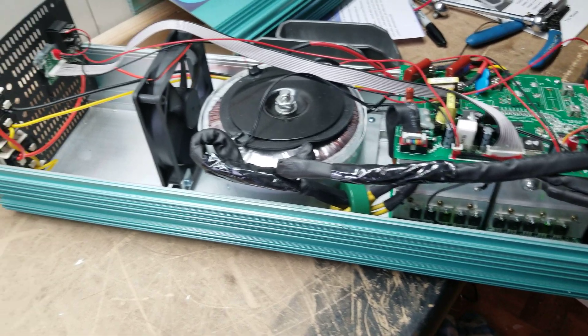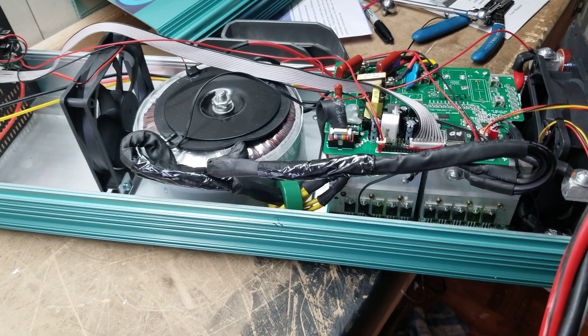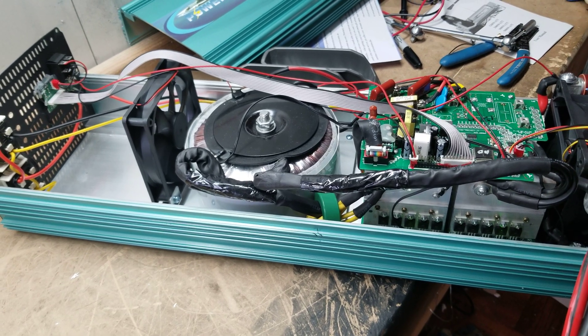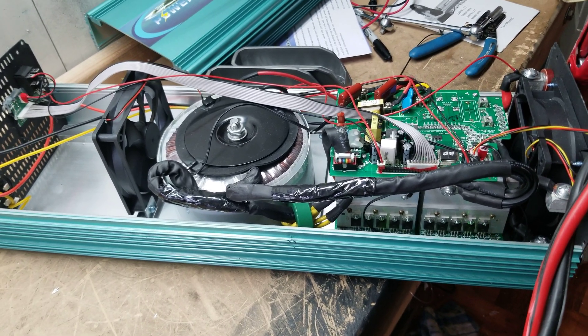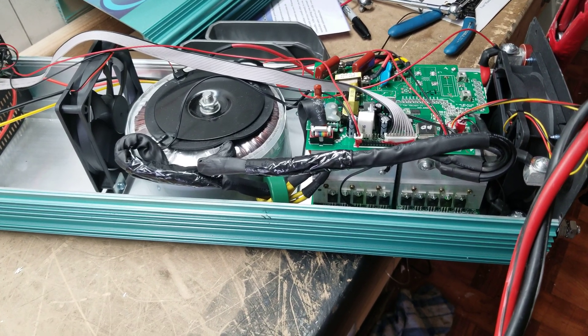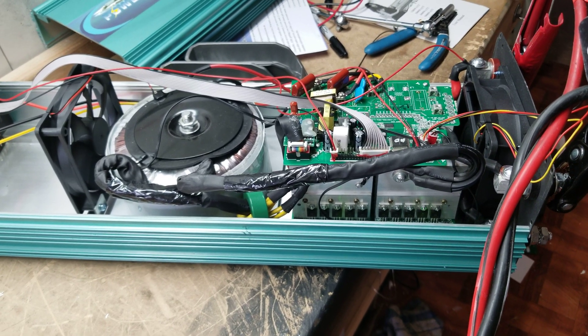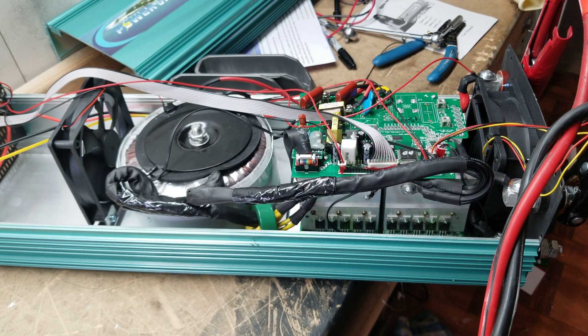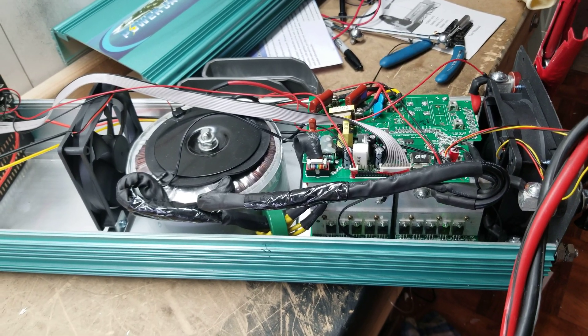You have room in here to add a whole other transformer, or go for a long-style mainboard — there's a ton of room in here. I like sharing these old inverters; I think they're pretty cool, looking back to see how far they've come versus today. The modular system was definitely the biggest thing they could have done for their inverters. There are a lot of times when I just have to replace a low frequency driver or a power source board.